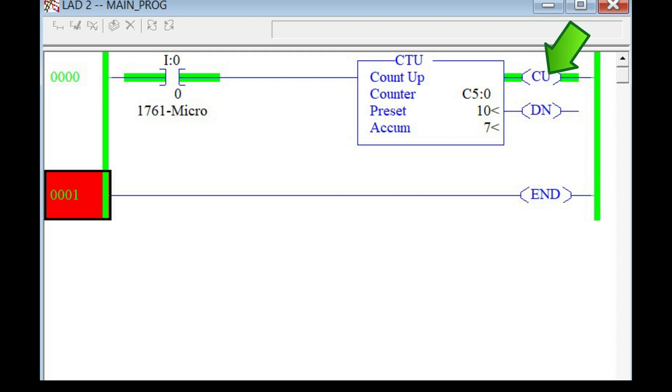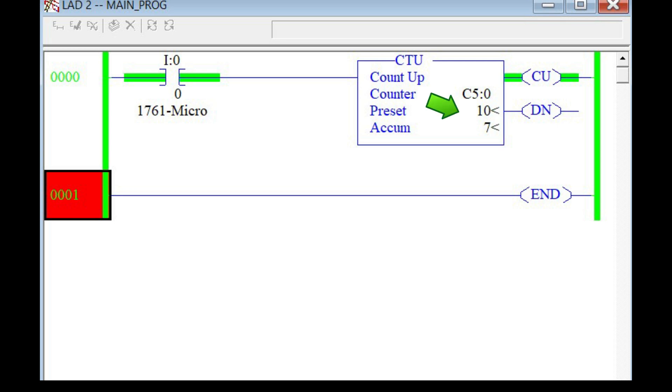The counter up bit, or CU, is set when rung conditions are true and remains true until the rung goes false or until the reset instruction is enabled. The done bit is set when the accumulated value is equal to or greater than the preset value, and is reset when the accumulated value is less than the preset.